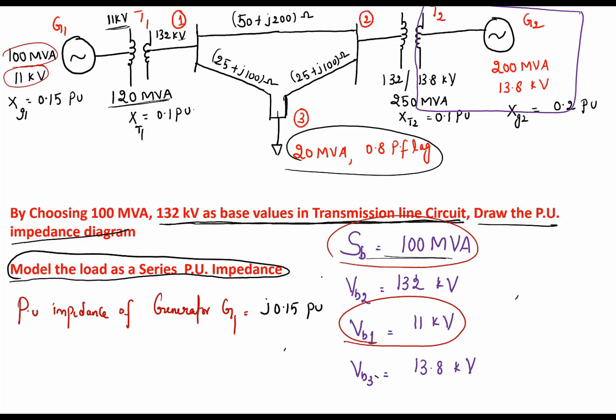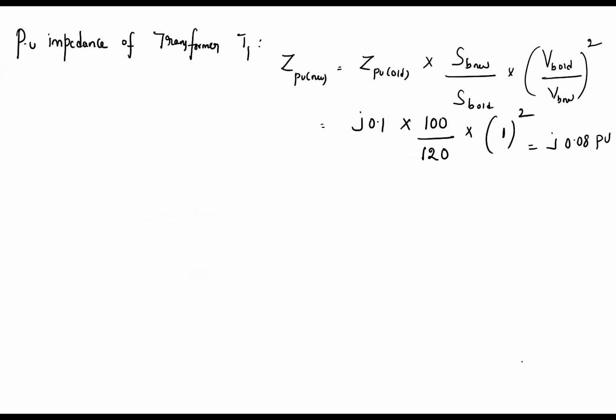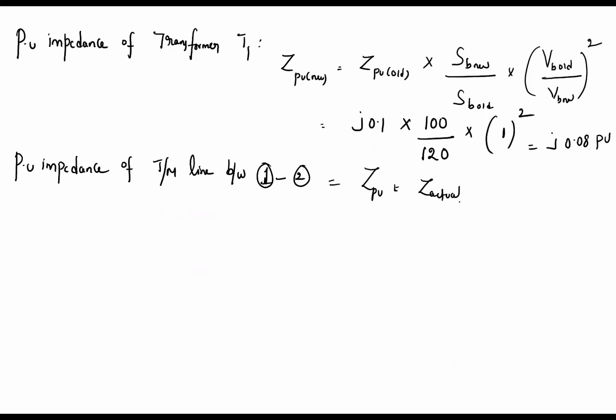Now we have 3 transmission lines. One transmission line is connected between bus bar 1 and bus bar 2, and the others between bus bars 1 and 3 and 2 and 3. Here the direct impedance is given. When impedance is given, to calculate the per unit value, which formula do you use? The per unit impedance of the transmission line between bus bar 1 and 2: Z per unit will become Z actual divided by Z base, that is Z actual into S base divided by VB square. So I am directly writing the formula. So what will the Z per unit value become?